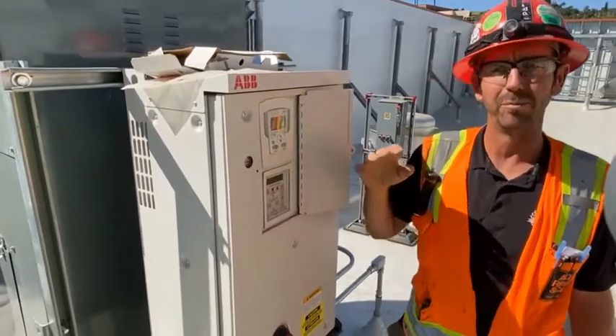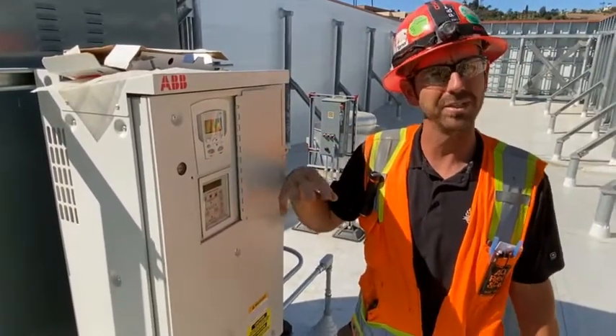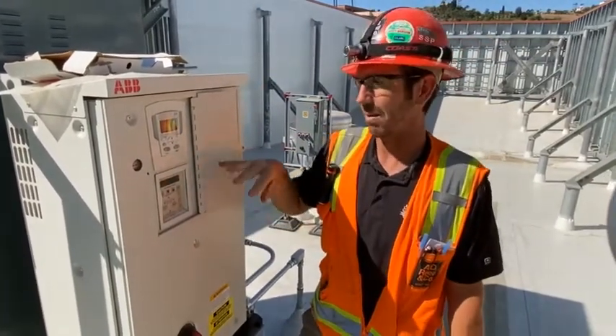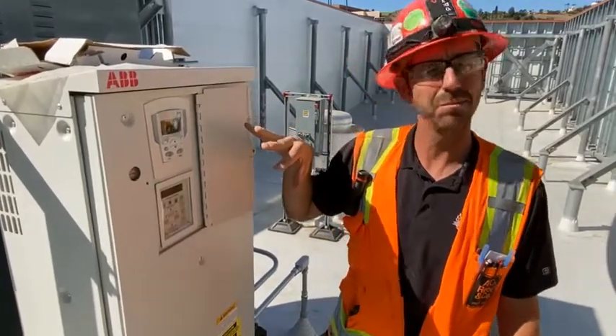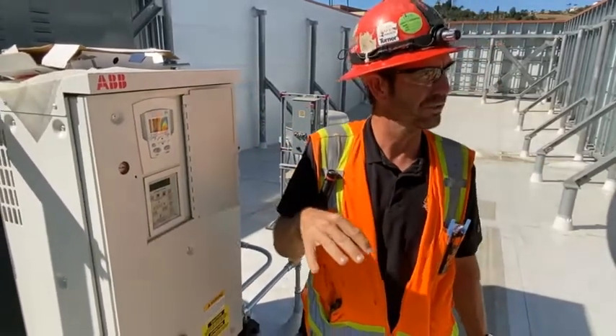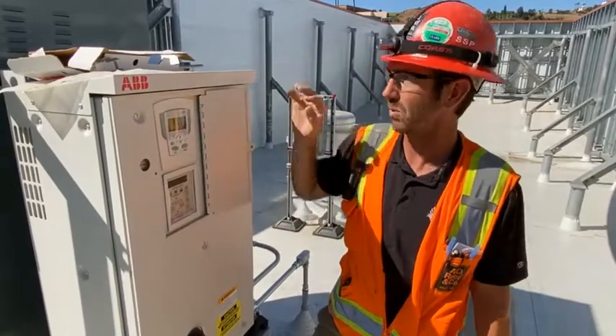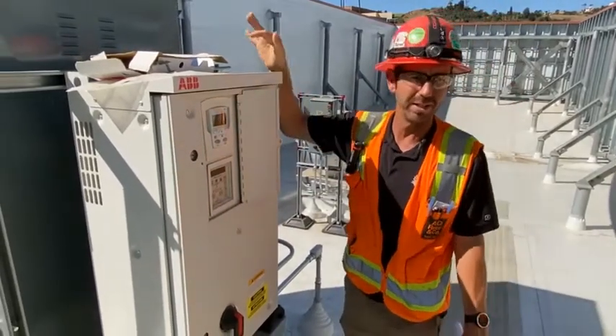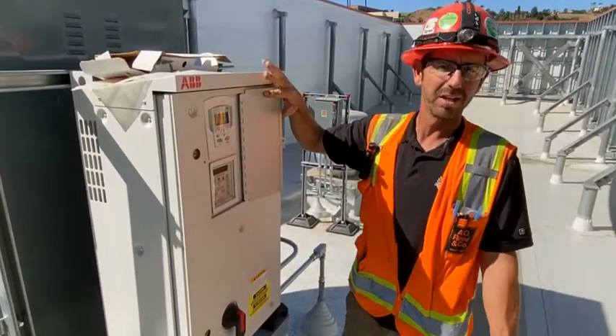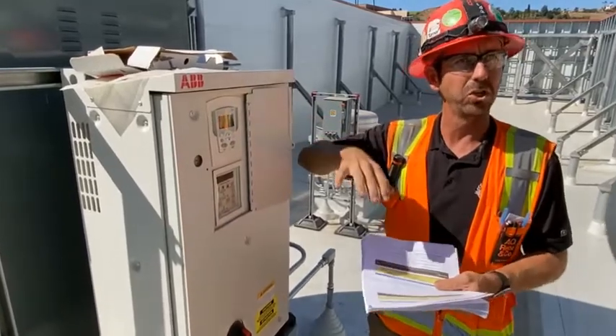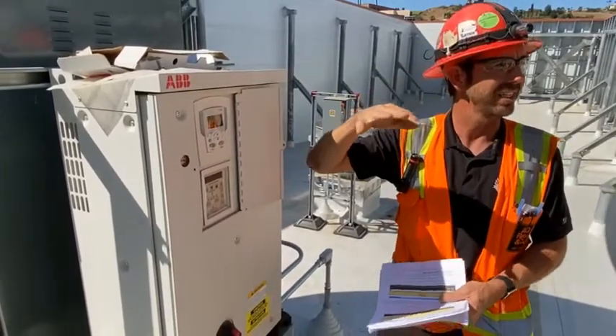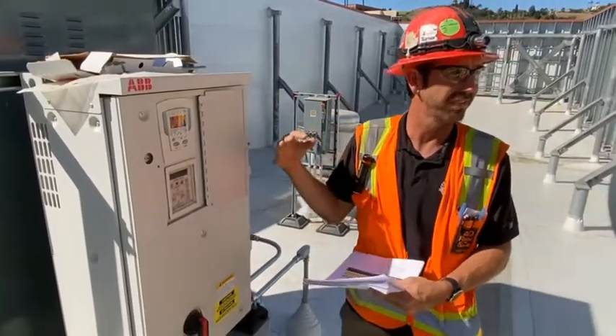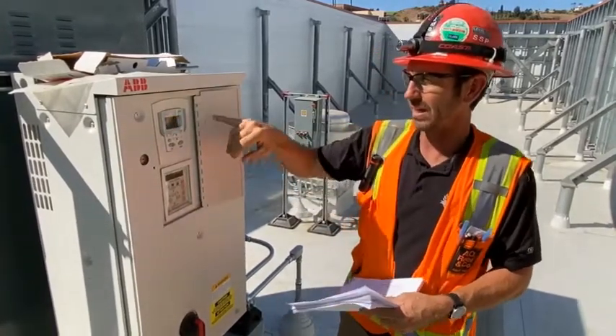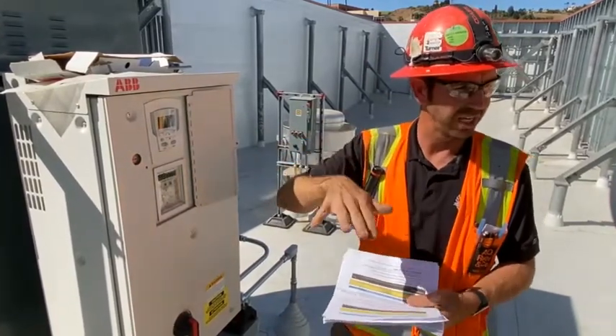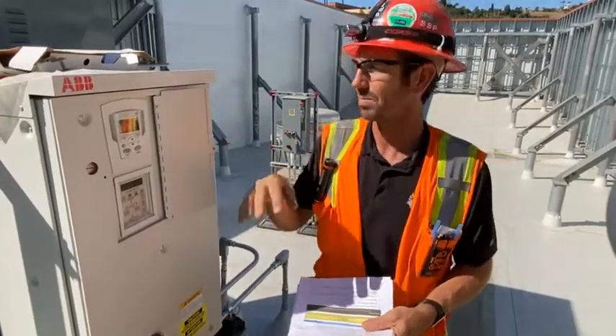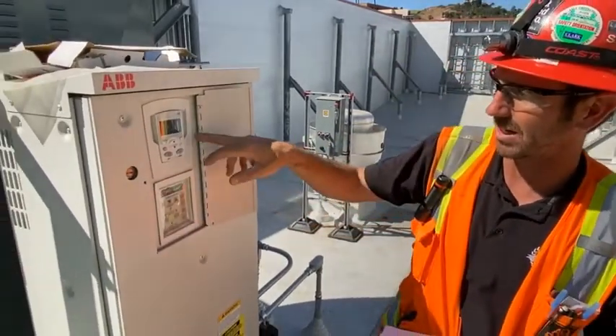We're up on the water heater side of Building D roof right now. On the fan systems that are on Building D roofs, either side, there's only one piece of equipment, EF1D, that has a VFD on it. So to tune the amount of exhaust they needed for the hood downstairs that this fan serves, they chose a VFD so we can change the operating speed, okay? That's already been logged into the unit.